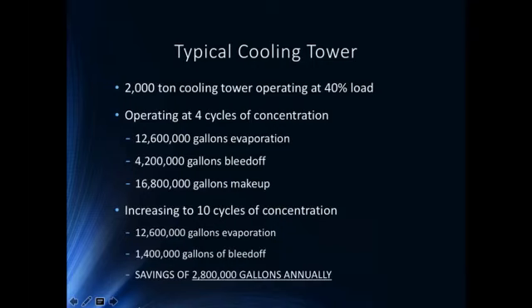4.2 million gallons are going to be lost through controlled bleed off, that we have to get rid of to be sure that there aren't some scale issues, which equates to a total of about 16.8 million gallons of makeup water. A lot of people don't realize that when you talk about the makeup water to a cooling tower, a very high amount of it goes through evaporation. And something that Ben mentioned earlier is a lot of municipalities give credits for the amount of water that's evaporated, because in a lot of places you're paying a separate charge for the sewer fee and the makeup fee. So the water that's evaporated, you shouldn't be charged sewer fees because it doesn't go through the sewer.